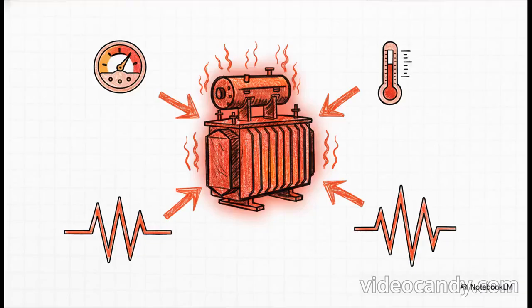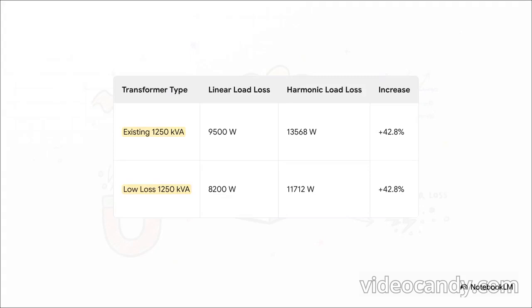Okay, let's put it all together. Achieving true efficiency isn't just about building a good transformer in a lab. It's all about understanding how it's actually going to be used out in the messy, complicated, and increasingly digital real world. So when you really look at it, you realize that transformer efficiency isn't just one single number. It's a constantly shifting target. You have to think about how hard it's being loaded, how hot it's getting, the power factor of the load, any voltage swings, and of course all those current harmonics from our modern gadgets. All of these things create a really complex puzzle that engineers have to solve to keep waste to an absolute minimum. And here's what that puzzle looks like in real numbers.